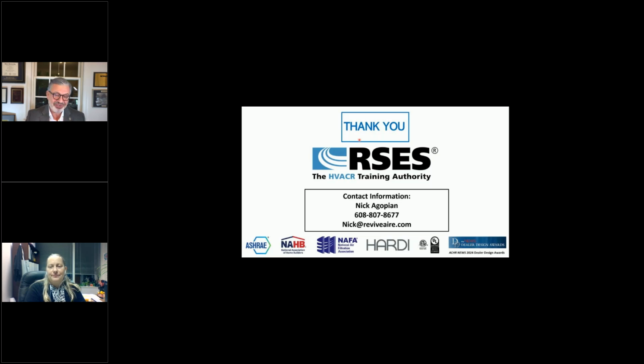I actually have a picture in another presentation of a person handling a contaminated filter, and there's a huge amount of discussion right now within the committees at ASHRAE on servicing these filters. If you're servicing a filter in a senior citizen's home or a daycare center, and there's a potential the virus could be in there because people were infected, it's considered a biohazard. You have to be gowned up, have the right gloves, eye protection, and respiratory protection. You can't handle those filters because they could infect you if the virus is on that filter, without a doubt. That's why so many people are moving away from standard particulate filters for pathogen control and saying you need to use an electronic device.